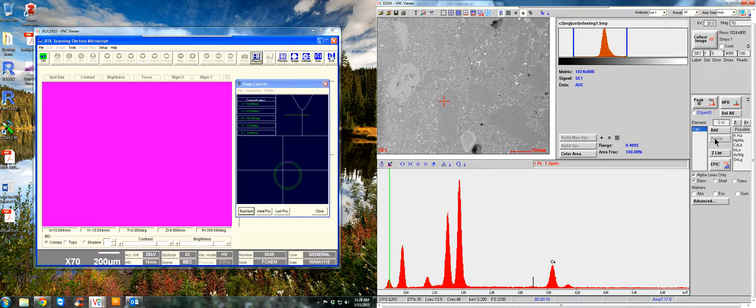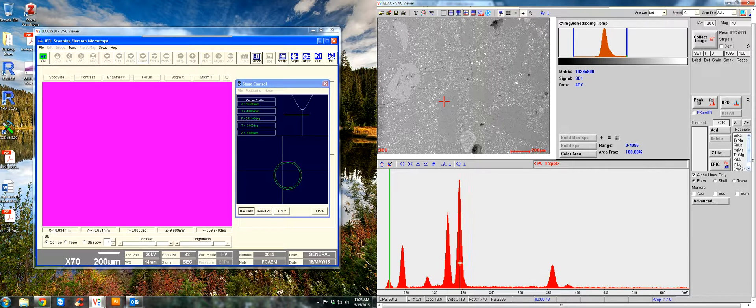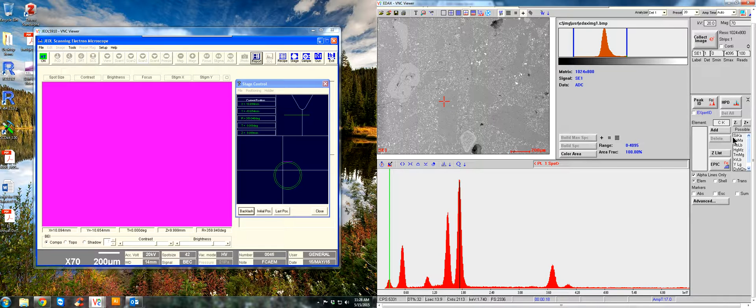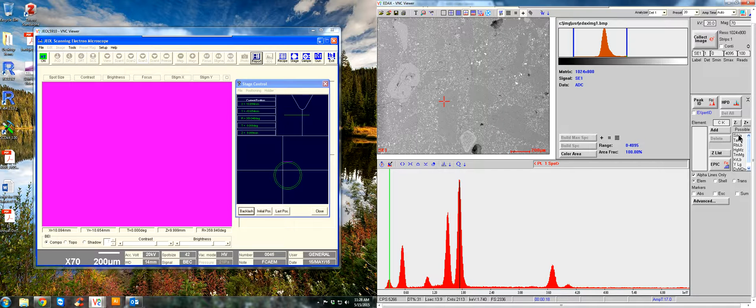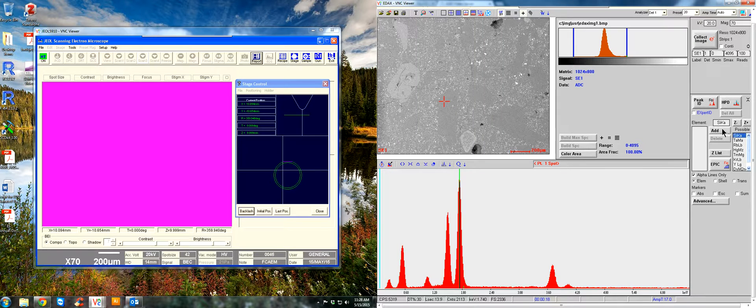So if you were to manually identify these peaks, you can use your mouse to click over, let's say, for this one right here. Click right at the middle of a peak. And in this box, it will give you the possible elements that have energy lines in that area. So in this case, it looks like a silicon K-alpha peak. So if you click on silicon, you can just add it.